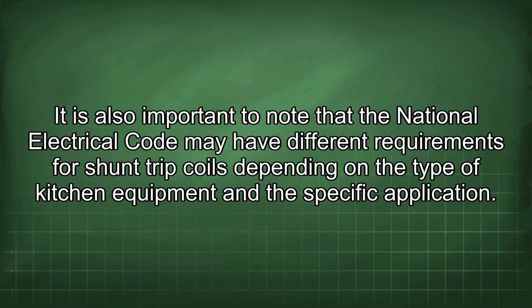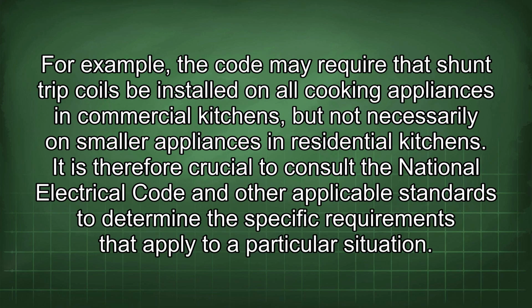It is also important to note that the National Electrical Code may have different requirements for shunt trip coils depending on the type of kitchen equipment and the specific application. For example, the code may require that shunt trip coils be installed on all cooking appliances in commercial kitchens, but not necessarily on smaller appliances in residential kitchens. It is therefore crucial to consult the National Electrical Code and other applicable standards to determine the specific requirements that apply to a particular situation.